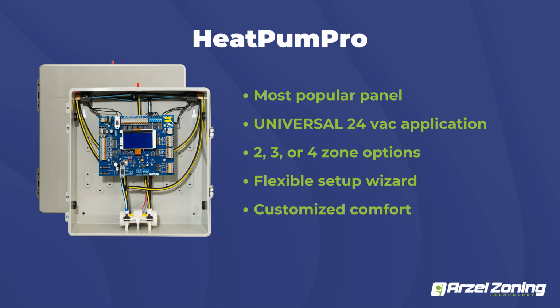And it's going to be able to provide you up to 4 heat, 2 cool on your outputs. And the way that this panel does this is it actually does all your staging based on leaving air temperature and runtime. So it's actually getting a real time reading in your ductwork as well as an outdoor sensor, which both ship with your panel. And that's how it's going to stage your equipment.